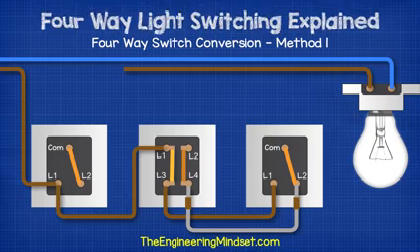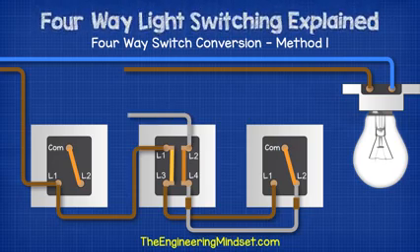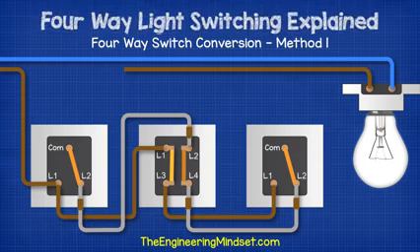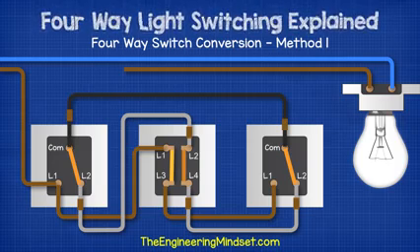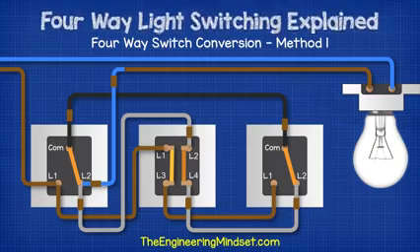We'll place a brown sleeve on the wires to indicate that this is intermittently live. We then run another grey wire from L2 of switch 2 to L2 of switch 1. We then join the 2 end switches with a black wire to each common. We'll then connect the blue wire from L2 of switch 1 to the light circuit.